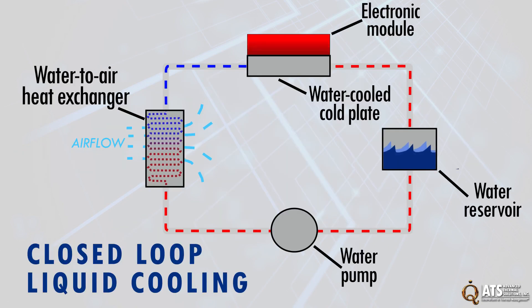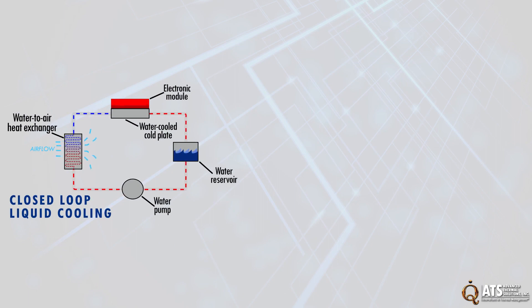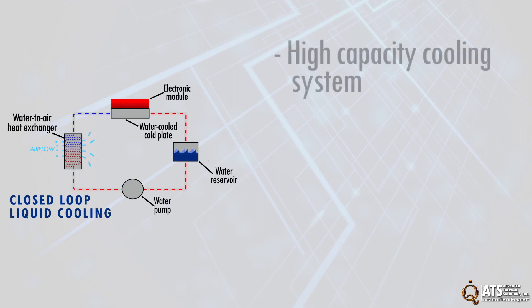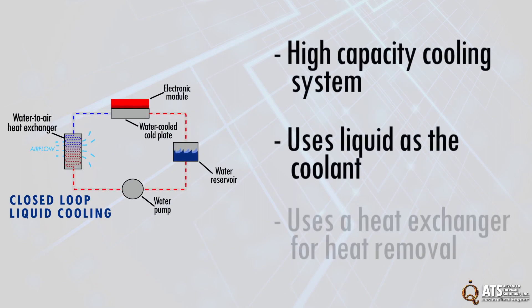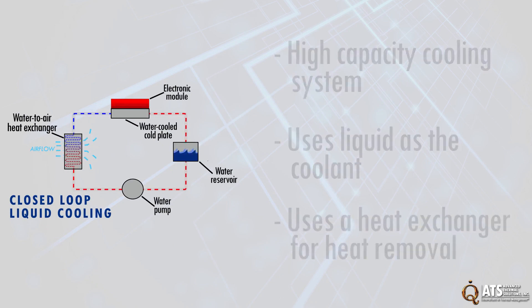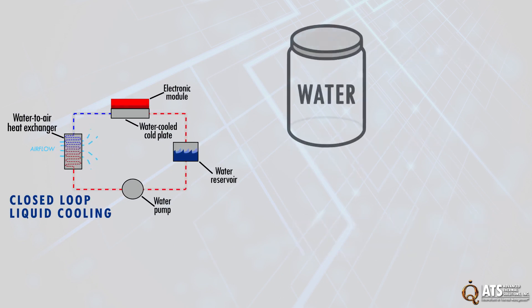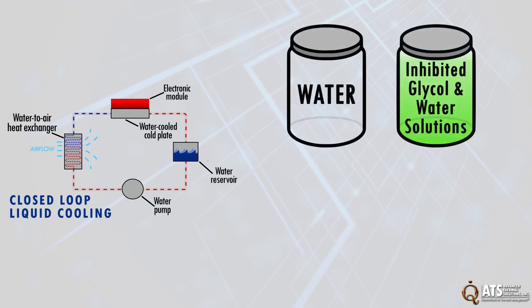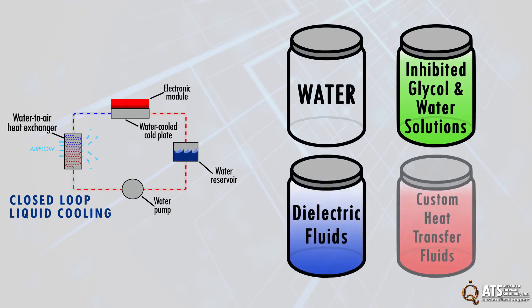Cold plates are an integral part of closed-loop liquid cooling. This system is defined as a high-capacity cooling system that uses liquid as a coolant and a heat exchanger for heat removal from the coolant. The most commonly used fluids are water, inhibited glycol and water solutions, dielectric fluids, and custom-designed transfer fluids.